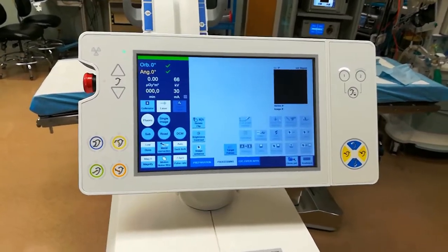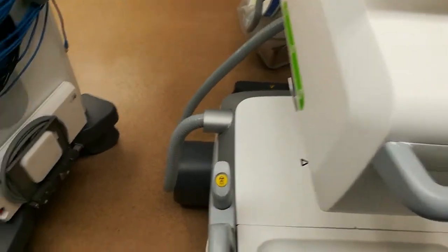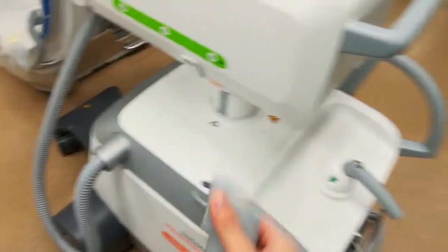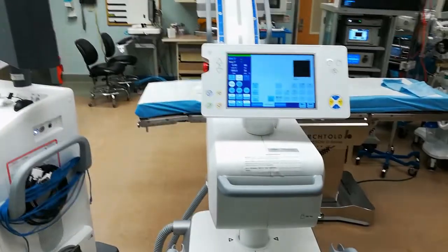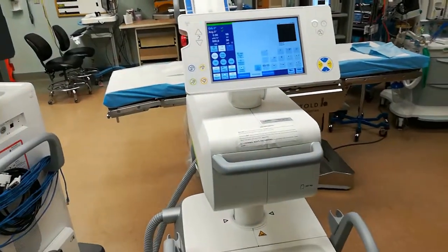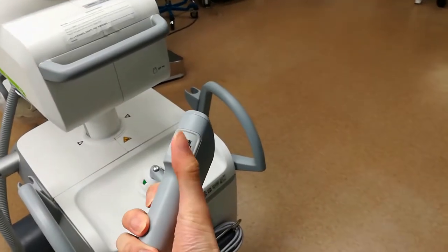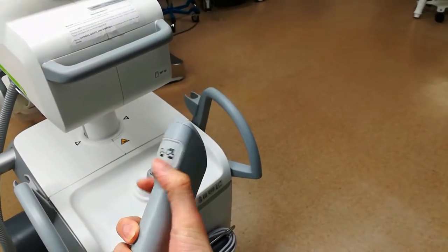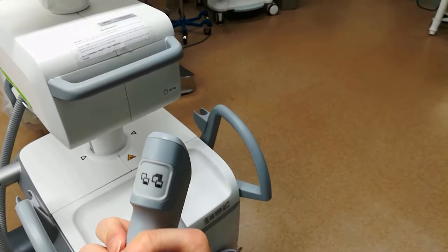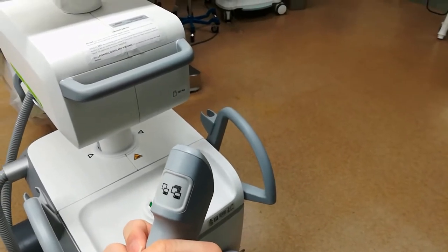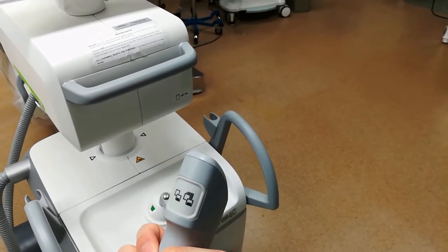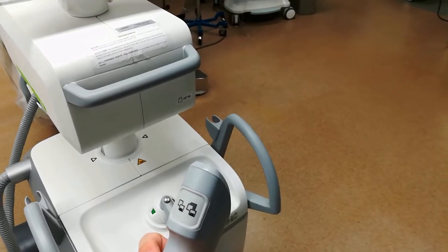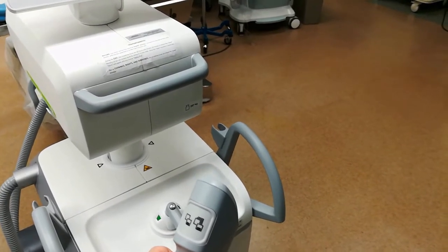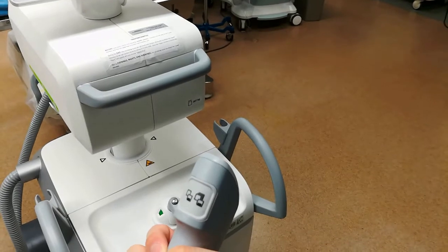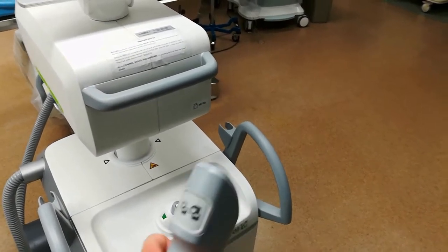The actual exposure button on the C-arm is on the handle here. It detaches, so you can save yourself some more dose by taking a couple steps back from the action while everybody radiates themselves. And then there's also this button on the front here where the trigger finger rests. Pressing it once saves a single image. Pressing it and holding it for 3 seconds saves the last fluoro run. Granted, they have to press the foot pedal before you get to save that run.